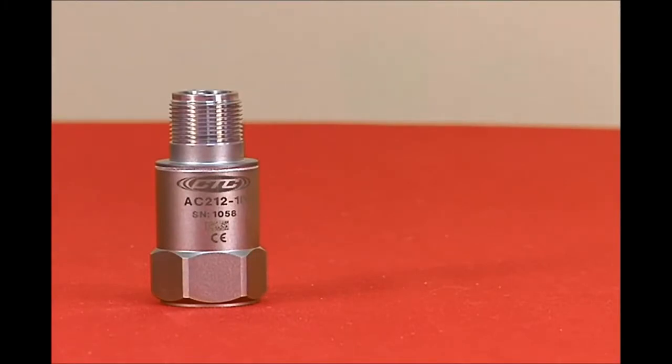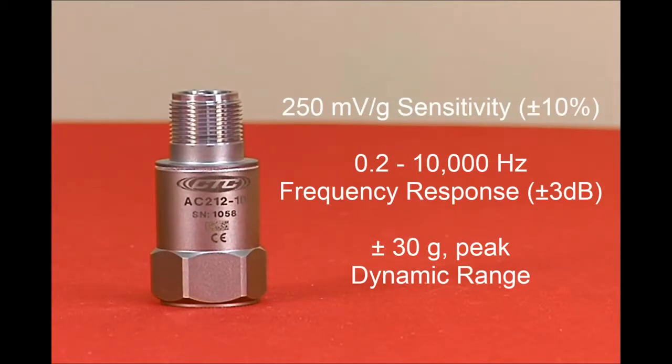The AC212-1D sensor is a plus or minus 10 percent sensor with a sensitivity of 250 millivolts per G. The frequency response goes from 0.2 hertz to 10 kilohertz, 12 cycles per minute to 600,000 cycles per minute. The dynamic range is plus or minus 30 G's peak.